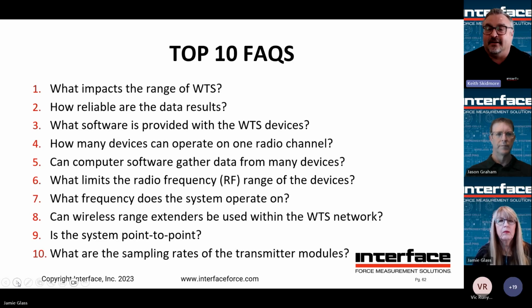You can take 100 readings, which would be about 500 milliseconds, and you can also specify how often it transmits. So you tell it to take readings for, say, 10 readings, and it averages those into one data point. If you tell it to transmit 200 times per second, that's 1 reading, send it, 1 reading, send it. But if you take readings for 50 milliseconds, that's 10 readings, and transmit once per second, it'll send the average of those 10 readings once per second. I don't know if that completely answers the question, but that's how it works.